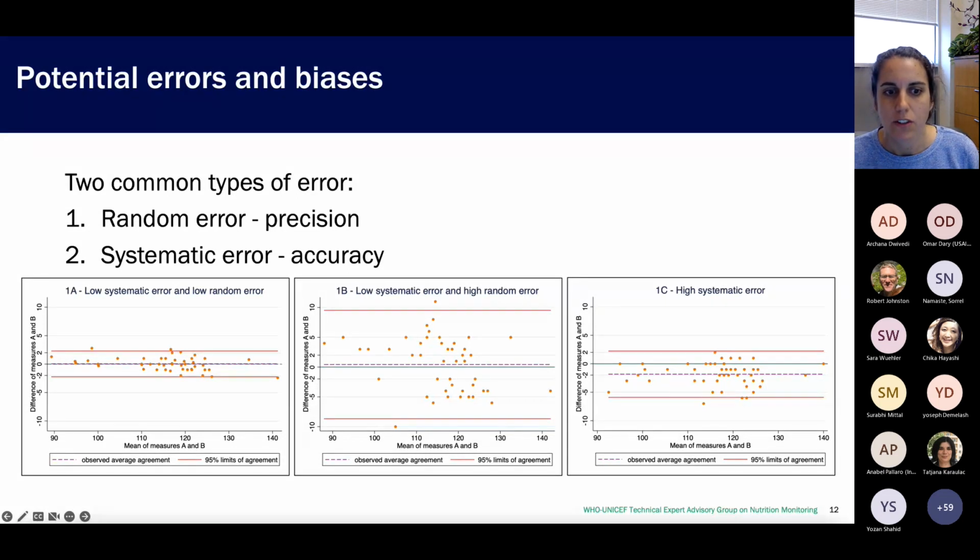An example of systematic bias is when a hemoglobinometer like a HemoCue device is consistently measuring hemoglobin slightly higher or slightly lower than the gold standard comparison, which would typically be an automated hemoglobin analyzer. This is an estimation of the accuracy of the method. If there's little to no bias, the dotted horizontal line would be close to 0.